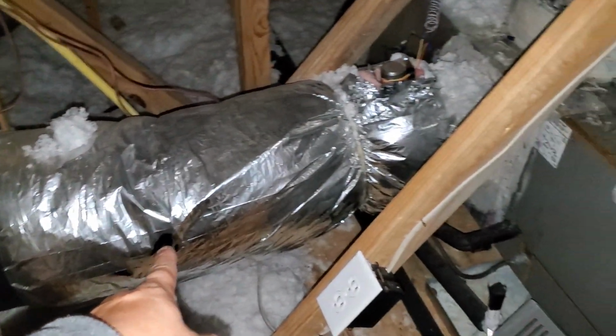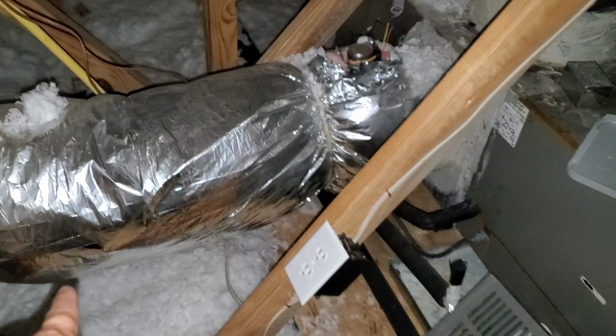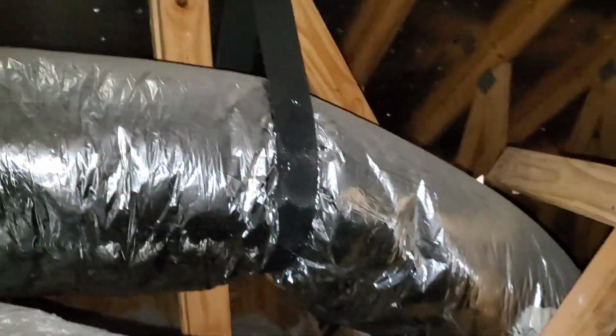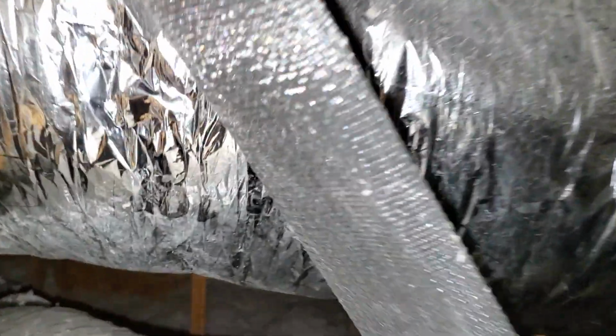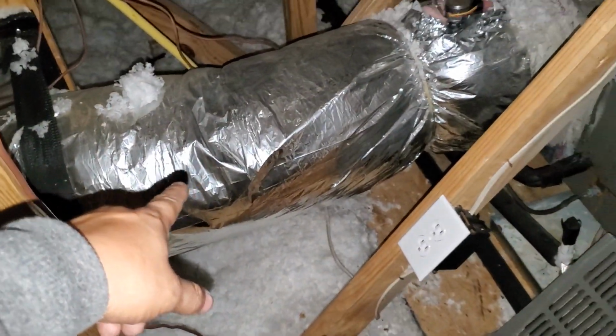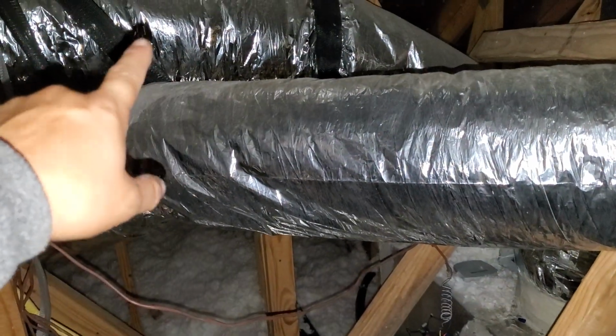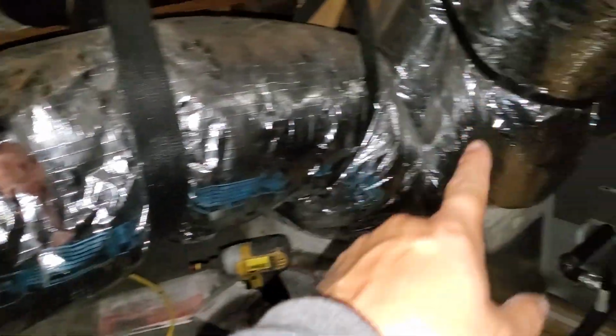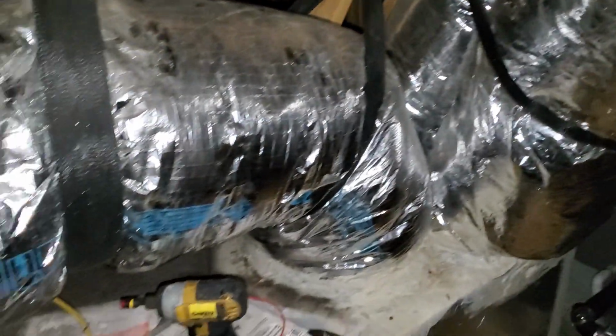Also have what appears to be 12 and another 12. Two zones. Oh, excuse me. That is in fact a 10. So we got a 10, a 10. You got two dampers. So two 10s, a 12-inch bypass, and two 10-inch returns. Obviously, this thing isn't going to work properly. It's been cycling on limit up here.